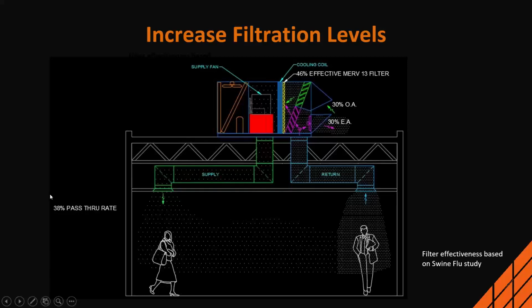You can see this makes a huge difference because now I'm down to a 38% pass-through rate, which means I've captured 62% of the virus particles overall between the outdoor air diluting them and then the filter actually capturing them. So 4 to 6 times an hour, we're pulling out 62% of the virus particles. So you can see, and this is actually graphically accurate, the densities here are really going down. Now these 2 steps we can implement on most of our buildings fairly easily, as soon as you get the filters and get someone to program the system.